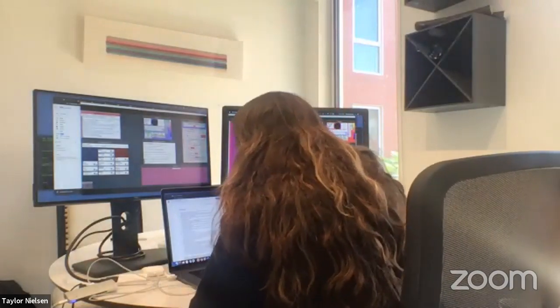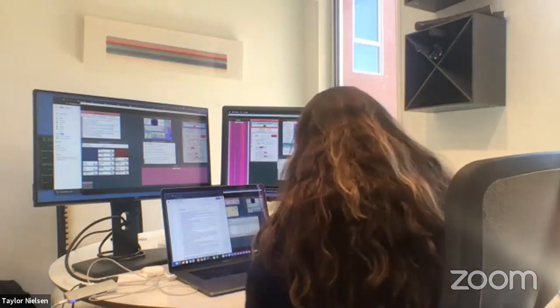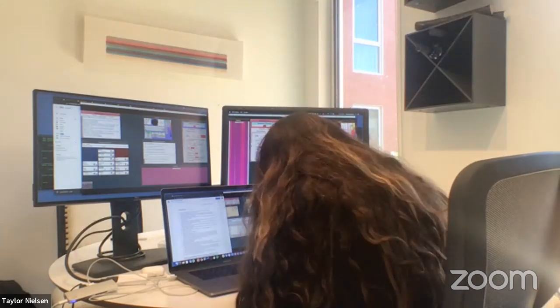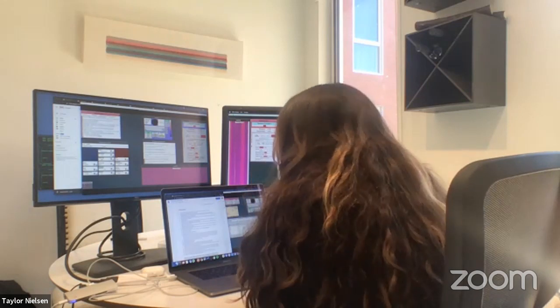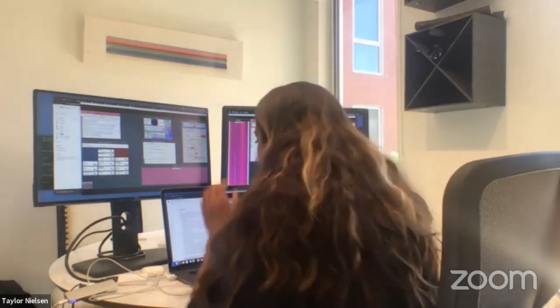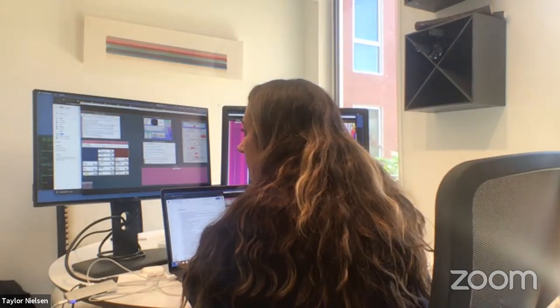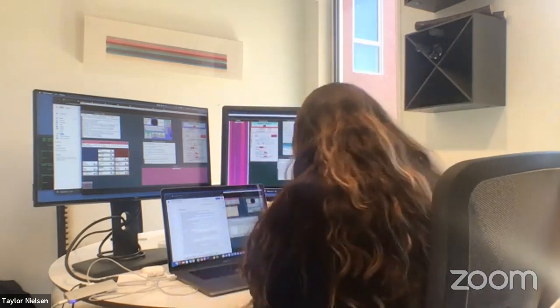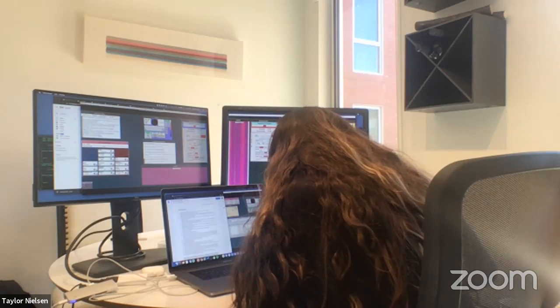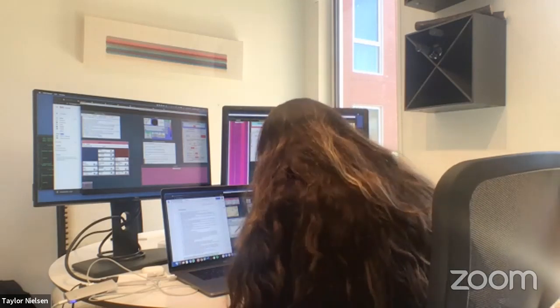Okay. So I'm going to write down the collimator values for the observations that I just took. So on the blue side, my collimator was 23.058, and on the red, it was negative 0.450. Now I'm going to decrease the collimator values. And then I'm going to write those down and take another exposure. All of this is to calibrate, so that's why we do this.